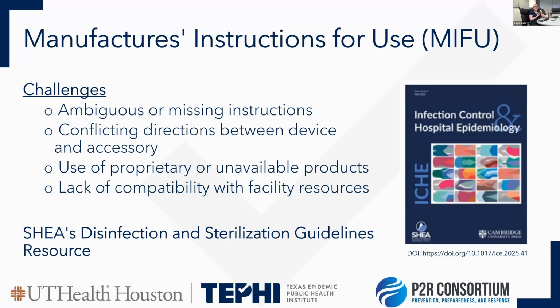Sometimes they are unavailable. So when you're purchasing, make sure you're looking at the IFUs or requesting them, and make sure you're not going forward without them. And then the last thing is lacking compatibility within your facility. So when you're getting a new device, if there are certain steps you have to do, do you have a designated specific sink or a certain type of cabinet? Do you have that cabinet, or is that a new cabinet you're going to have to buy to house that piece of equipment? And is that within the budget?